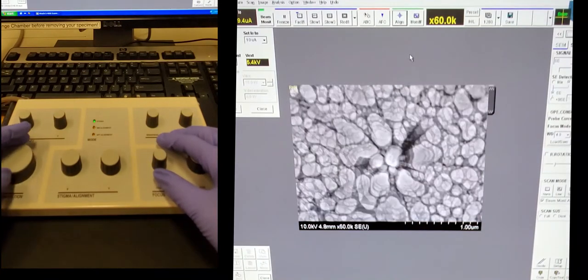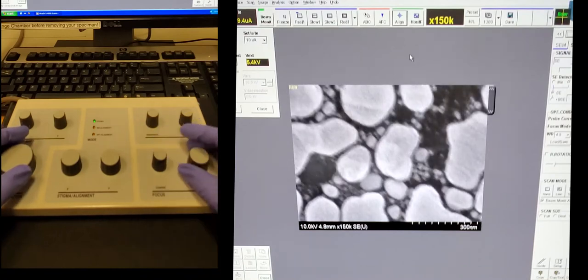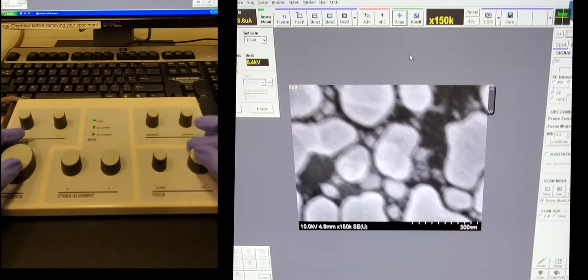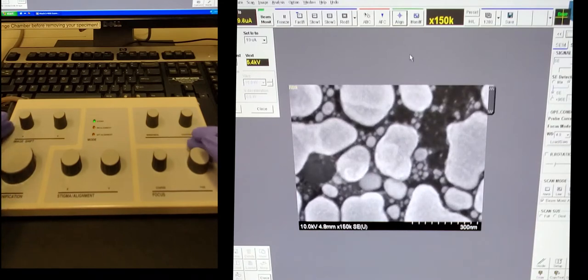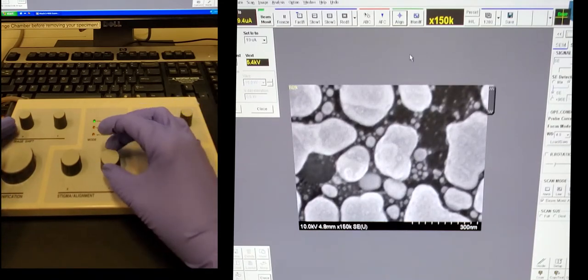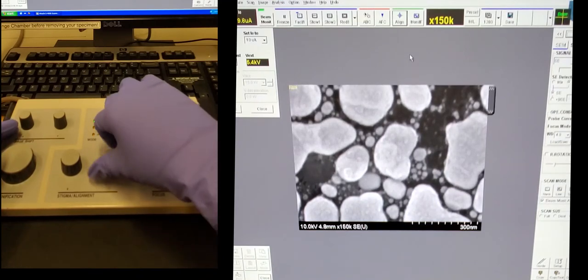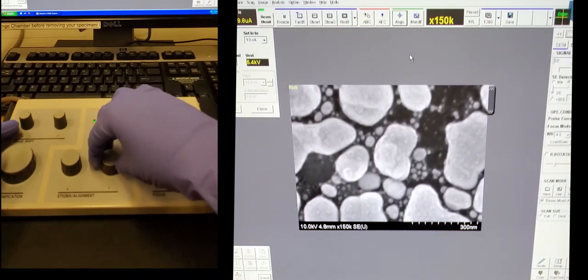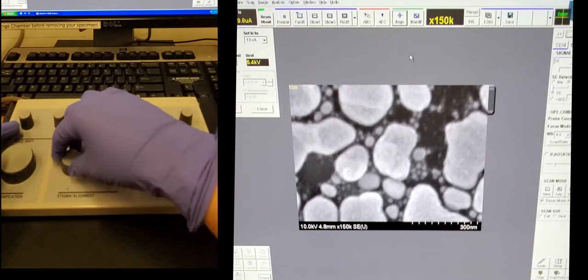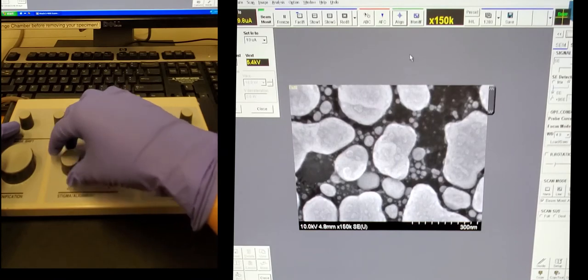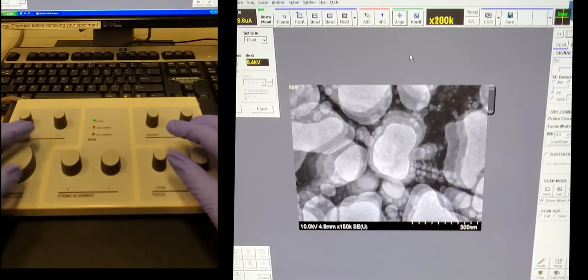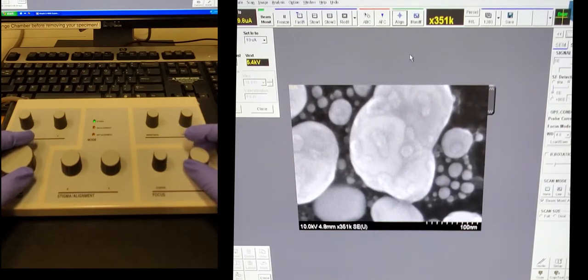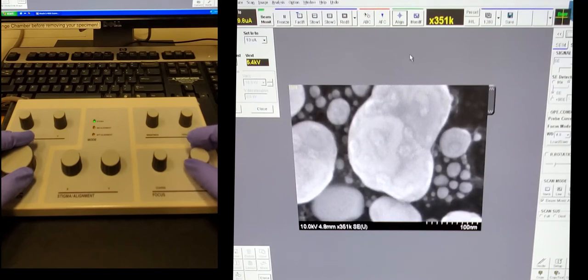And make sure we'll zoom in some more to do an extra sharp image adjustment. We're going to use that fine focus. Make sure the image is not stretched in either direction and then we will check the stigmatism. Turn it until it gets worse and then go back to the best spot. Then check the Y as well. It gets worse. Go back. It gets worse so we find that best position. And then go back and check your focus again.